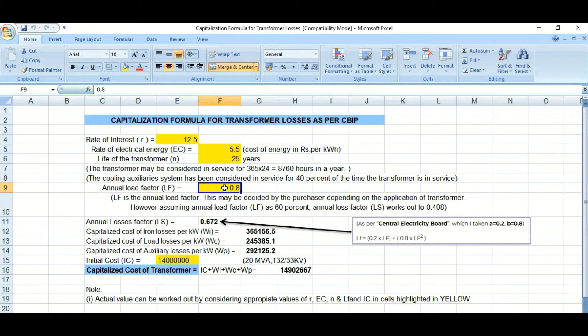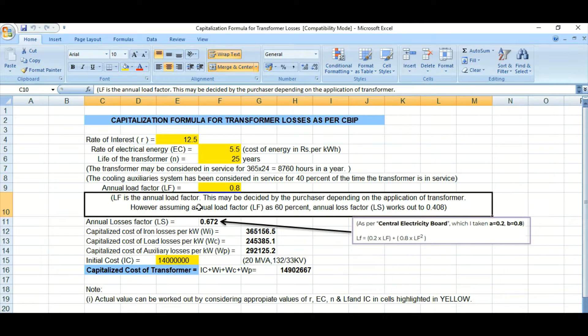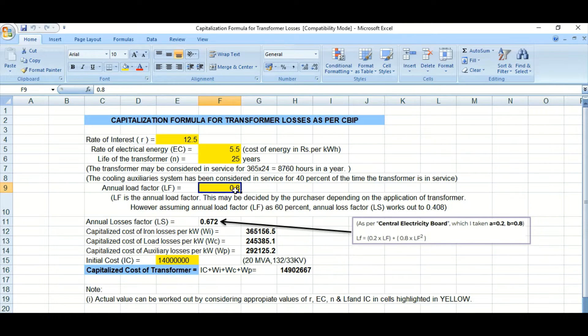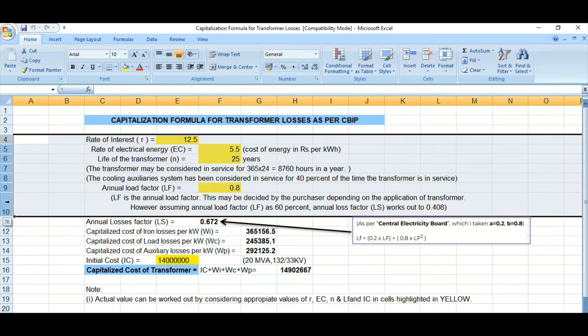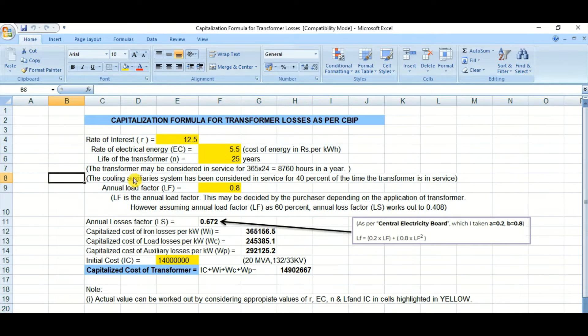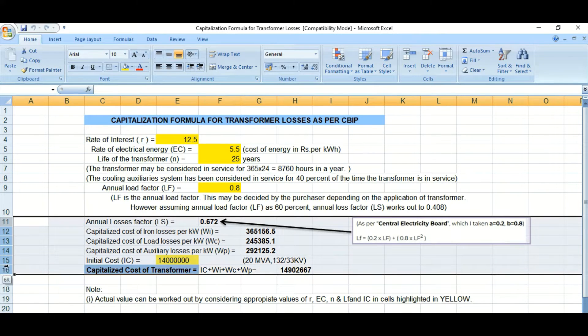The annual load factor is considered as 0.8, meaning 80%. It may be 0.6 or 60% depending on the plant load requirement. Here, 80% is used as the annual load factor. These are the input parameters and assumptions used to perform the transformer capitalization calculation.